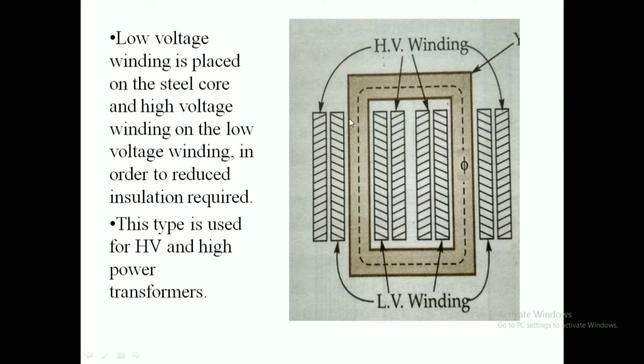If you see the inner section view of this winding, then we will find that the low voltage winding, 50% of the low voltage winding, which is placed over one leg, is just placed on the magnetic core. That means if this is the magnetic core, then this is the low voltage winding. Then 50% of the high voltage winding is wound over the low voltage winding.